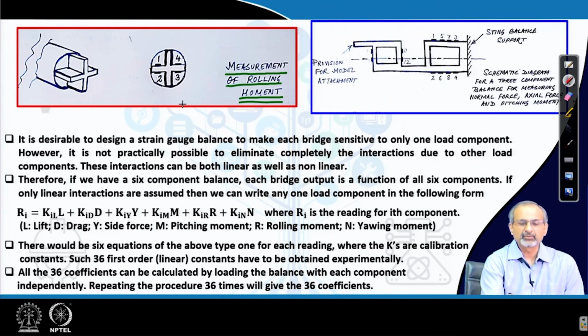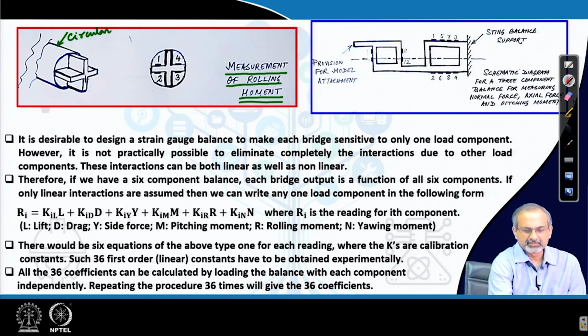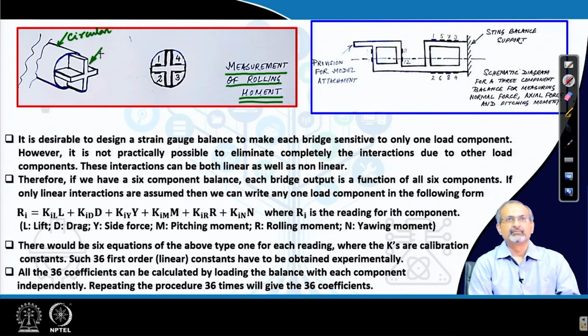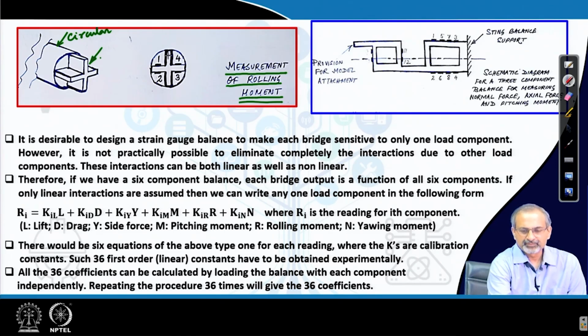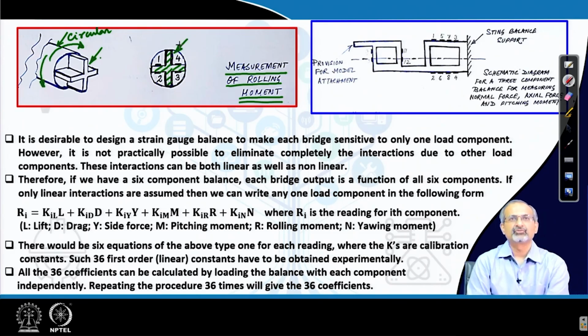Here the section is usually differently designed. Let us imagine that the main sting body is circular. If it is that way, then it is machined in a form like this in one part of it, where the strain gauges related to the rolling moment measurement are to be bonded onto the sting balance surface. So we find that some kind of a section like this is machined, and on the 4 surfaces, 4 strain gauges are mounted. Remember that when there is a rolling moment, it will tend to move like this or like this, and then a section of this kind will be much better sensitive in trying to record the rolling moment.